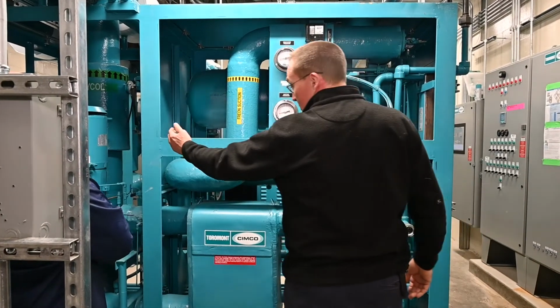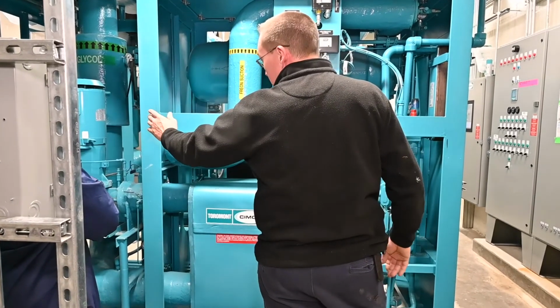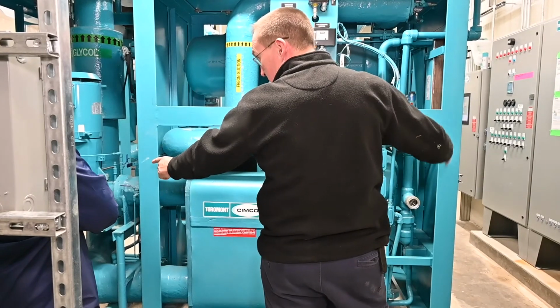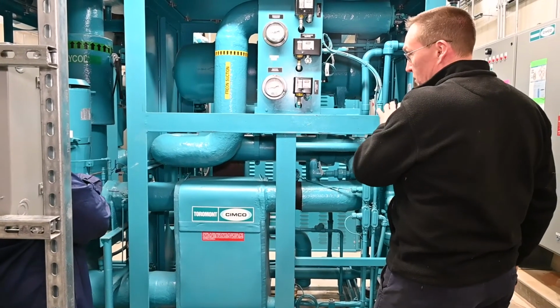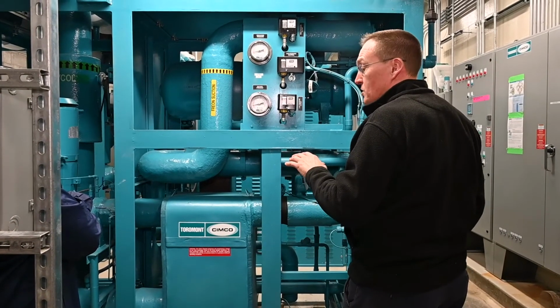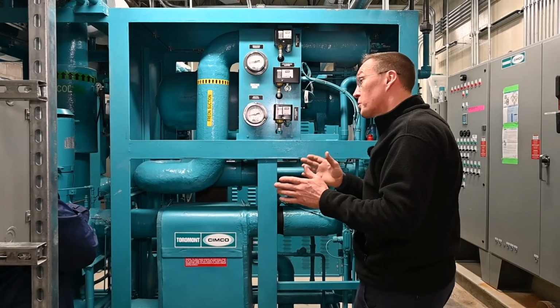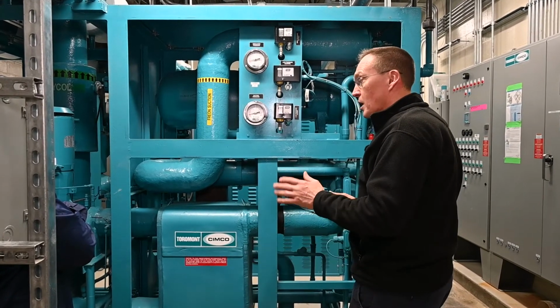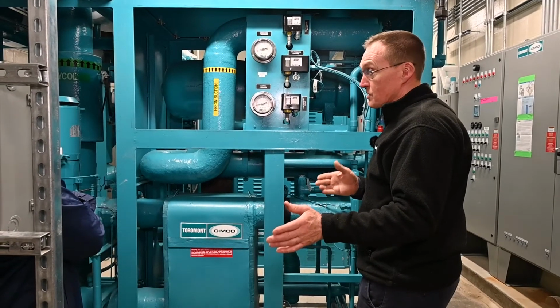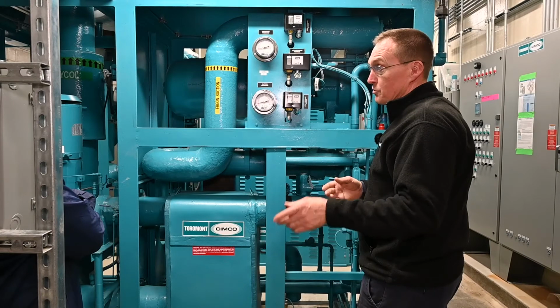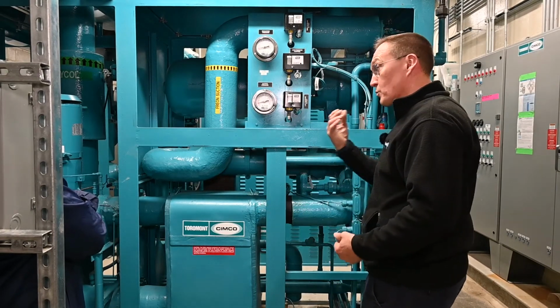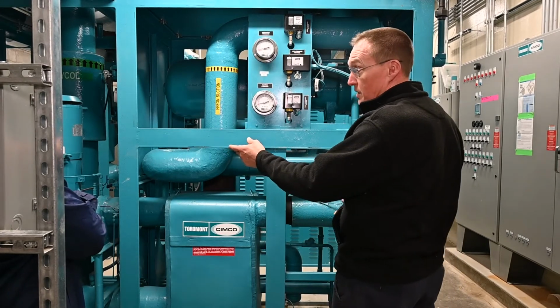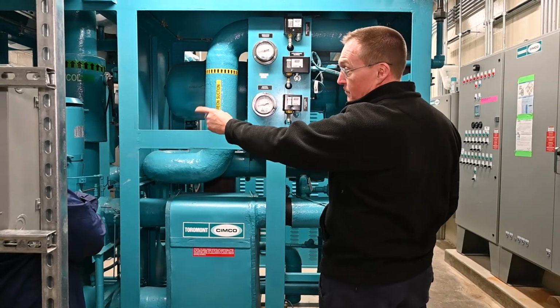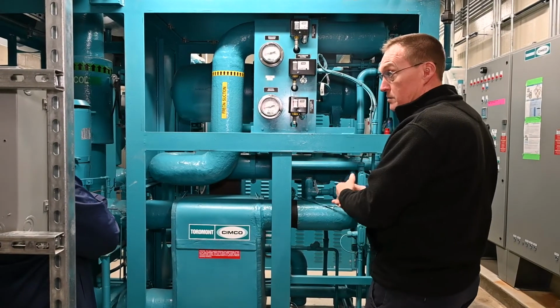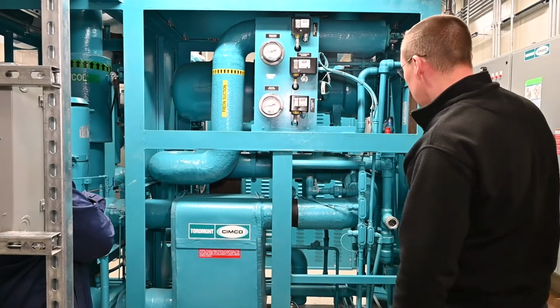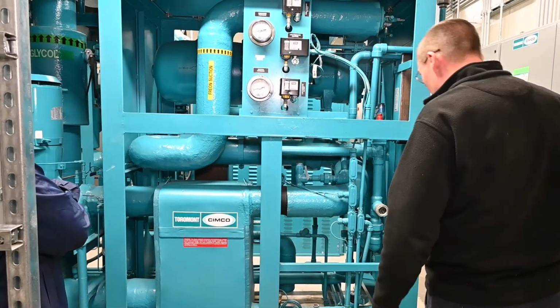What you're looking at here is your evaporator. As Matt explained to you, this is chiller unit number 1. This is labeled as a GP1 pump, and I'll show you that switch on the main panel. Base of operations for this unit: when the package first gets a call to start, depending on whether or not you're running the system in a return mode where your pump is run all the time, and on that note, on every cycle of temperature, if you're running on slab control, we will flip-flop on pumps. So you'll see first call will be pump 1, then the next call for cooling will be pump 2. And we do that for all of the pumps that are redundant. So pump 3, pump 4 on your warm glycol loop, pump 5, pump 6 on your condenser water will be cycled. All right. The other side, you have the compressor, and we'll walk around there for a minute.